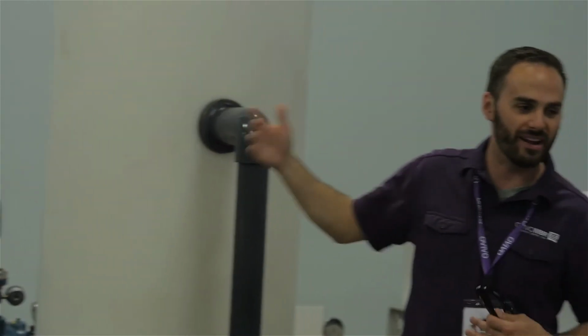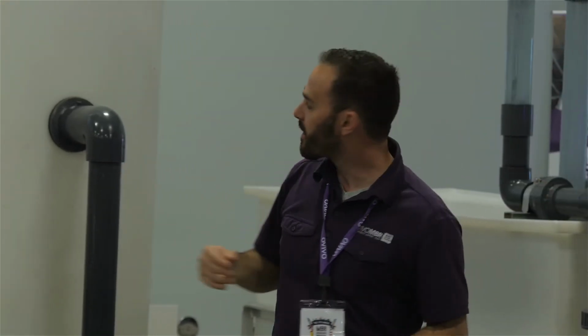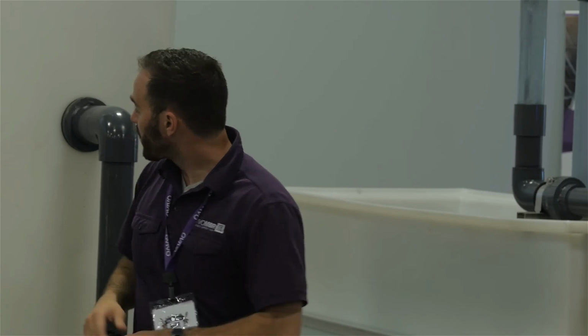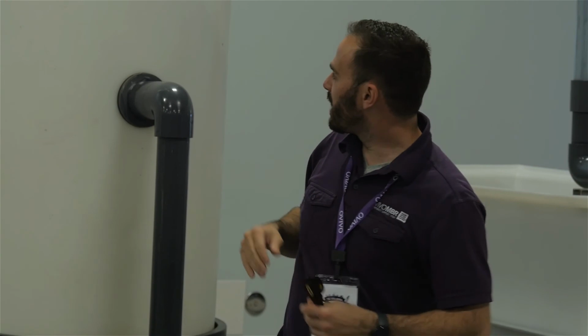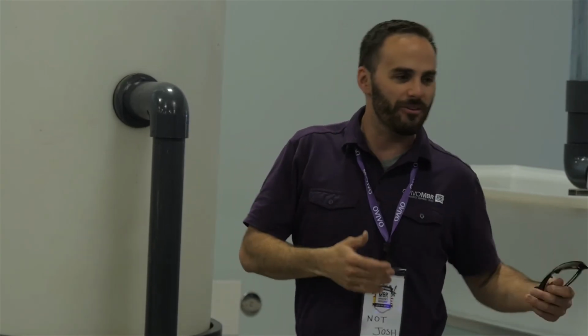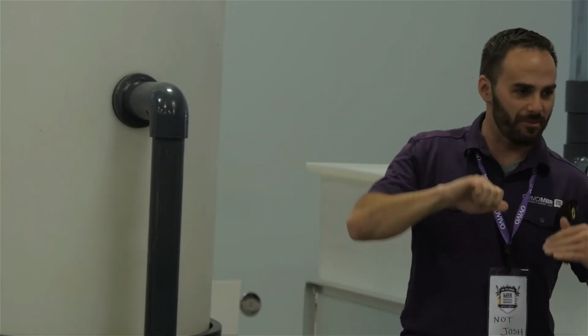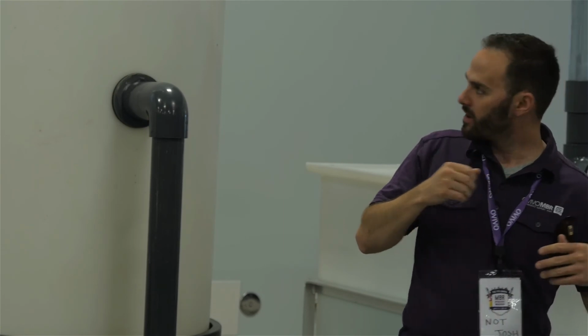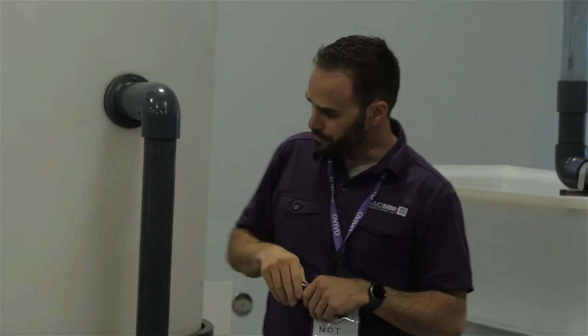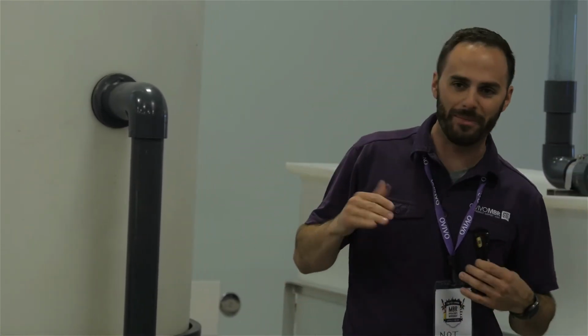Now, what's that going to do to our PLC and our pump? We're basically telling our PLC that our flow through the flow meter is going up and going down. And we would see that even if we had the pump locked in a manual pump speed, to be more specific. Even though we're not changing the pump speed, we would be seeing different flow rates.